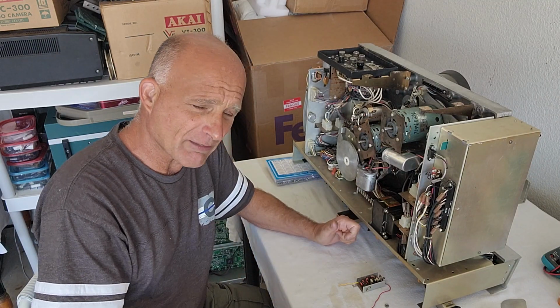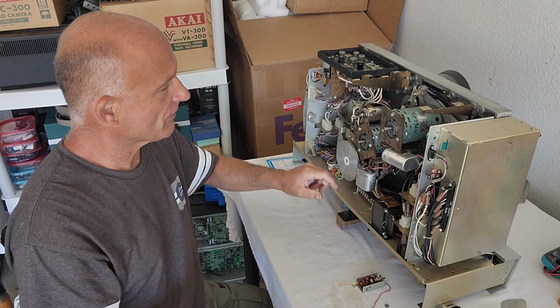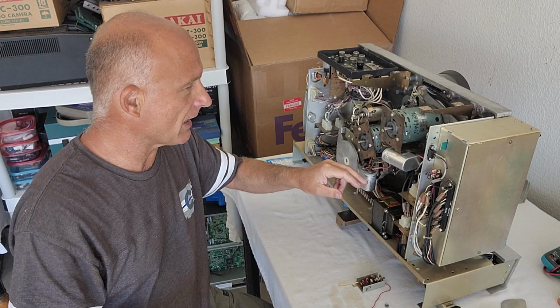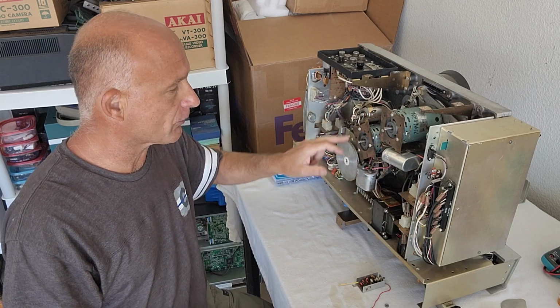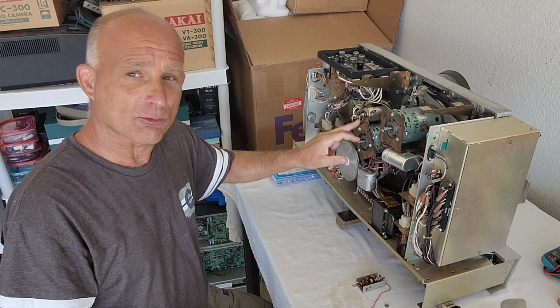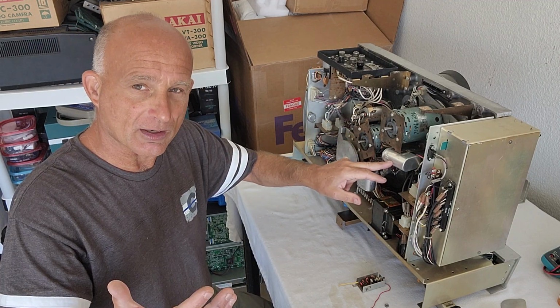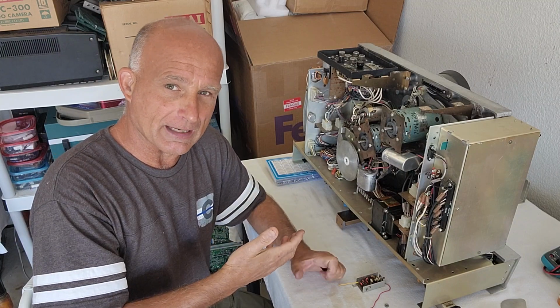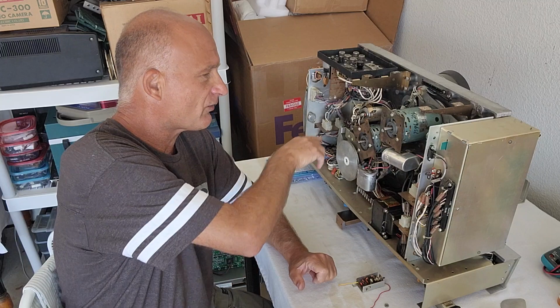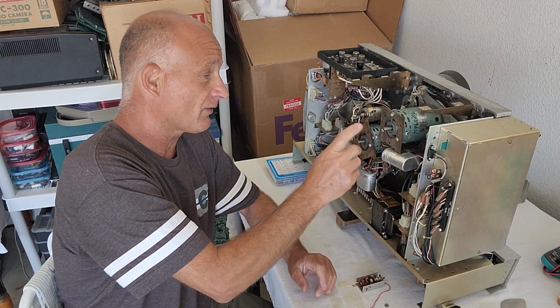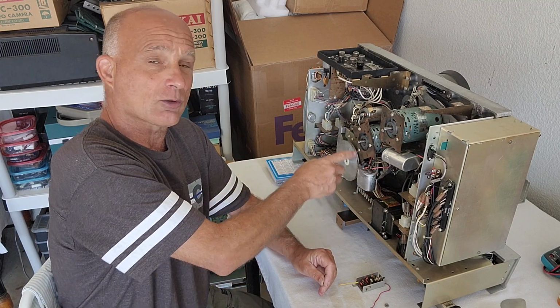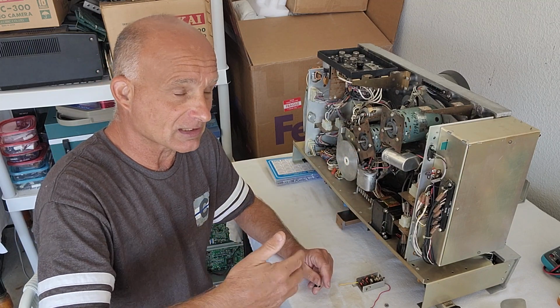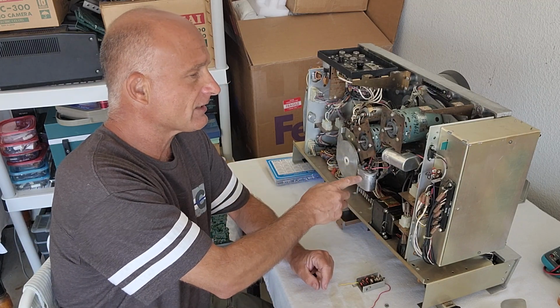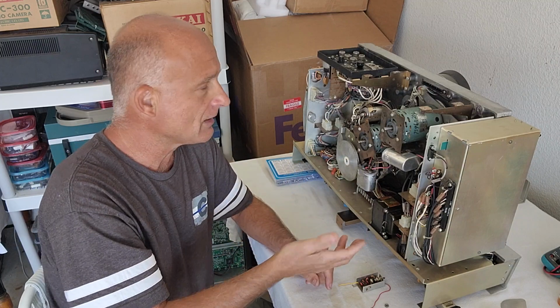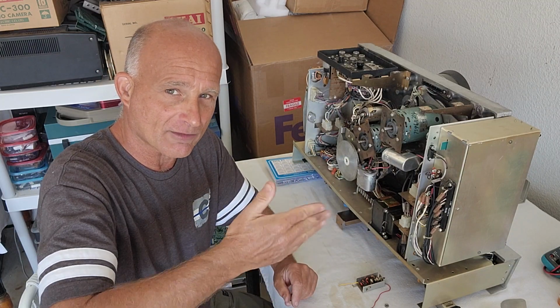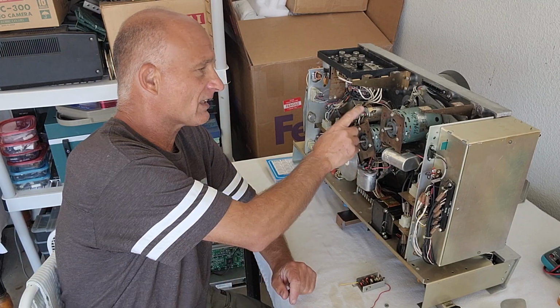Again guys, when you have a service manual, here's a perfect example. These capacitor values, the service manual shows 5 microfarads for all 3 of these. Well, these 2 capacitors are actually 3 microfarads, and only this one is 5 microfarads. See what I'm saying? You can't always go by what you're looking at. The service manual says 5 all the way around, but this thing says 3, 3, and 5. So it shows that a 3 microfarad capacitor will do the same job as the service manual says to use a 5. I guess the tolerances are just right to go back and forth between either one. Say you can't find a 5, you can easily find a 3, just buy 2 of them.